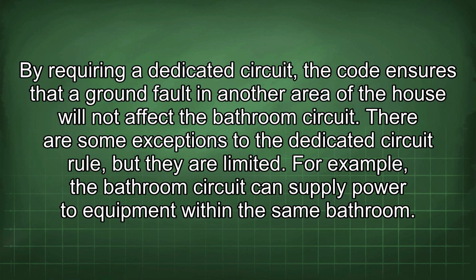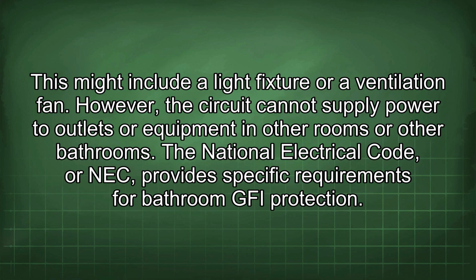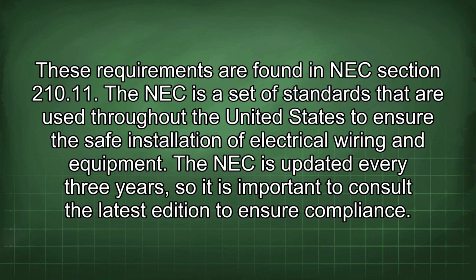For example, the bathroom circuit can supply power to equipment within the same bathroom. This might include a light fixture or a ventilation fan. However, the circuit cannot supply power to outlets or equipment in other rooms or other bathrooms. The National Electrical Code, or NEC, provides specific requirements for bathroom GFI protection. These requirements are found in NEC Section 210.11.